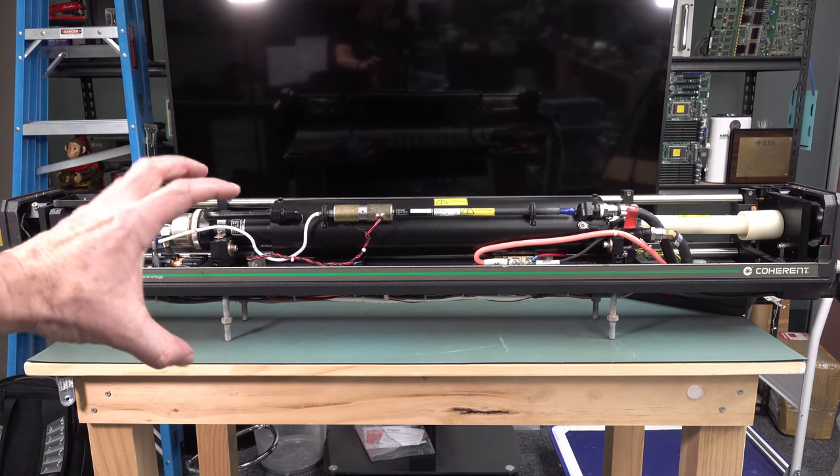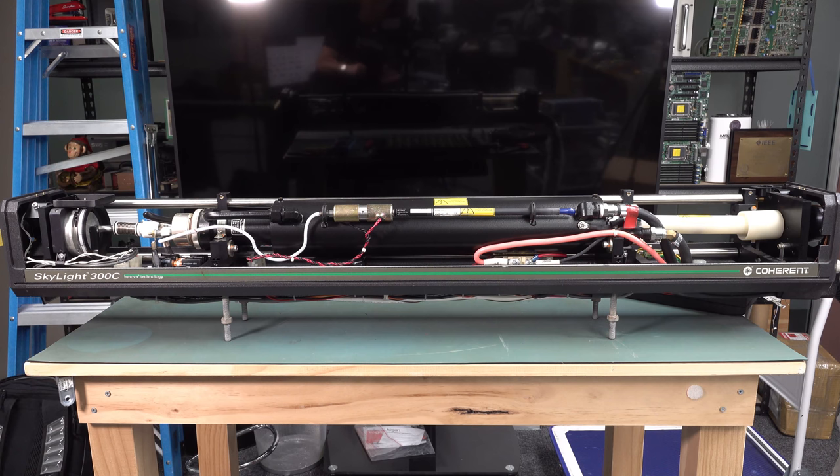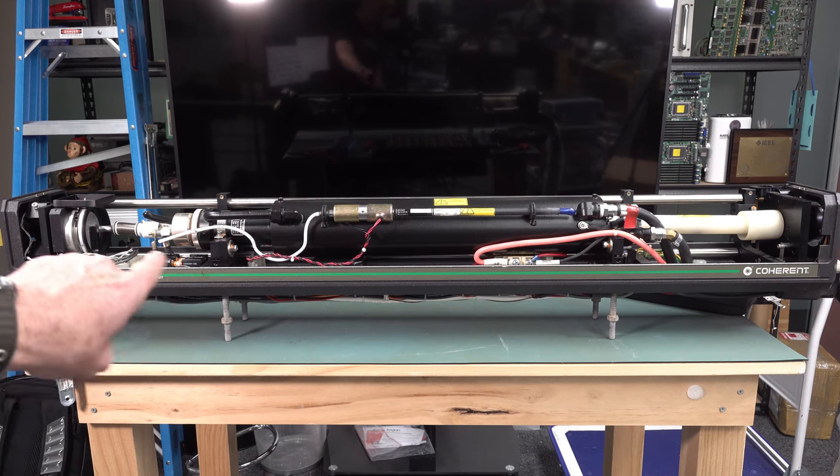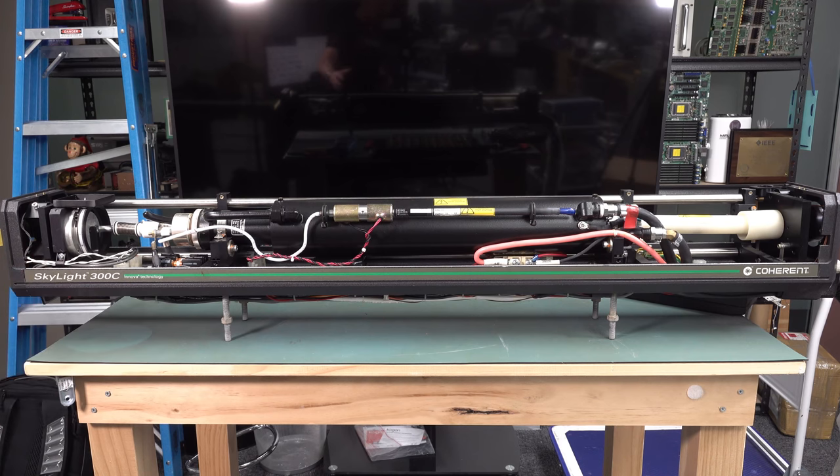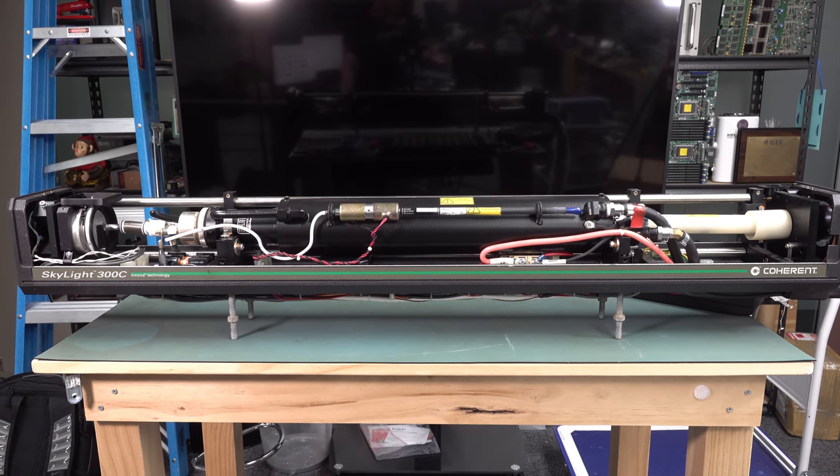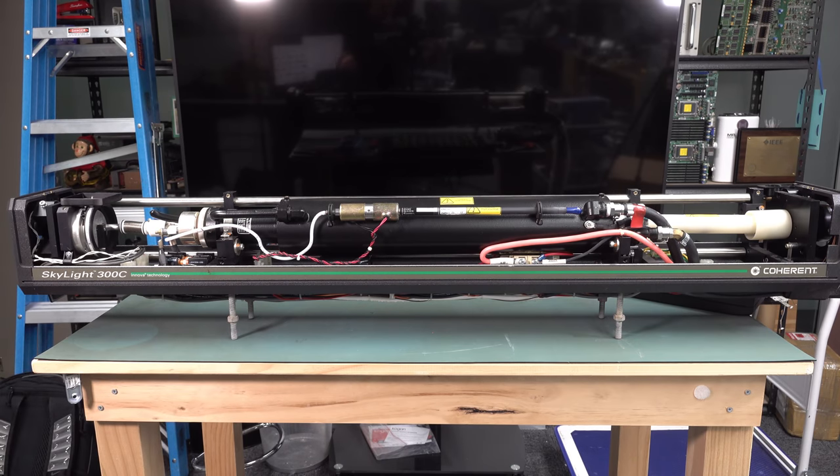So you provide, when you turn it on, you provide a brief high voltage surge to actually start the thing up to get the ions flowing in there. And once you do that, then the magnet contains it in there, and then the light bounces back and forth, back and forth, back and forth, and about 1% of it, a tiny fraction of it, goes out the front window like that. And that's basically how any of these ion lasers work. You just amplify the light in there by just bouncing it back and forth, back and forth, and then containing it with that magnetic field containing the plasma inside.